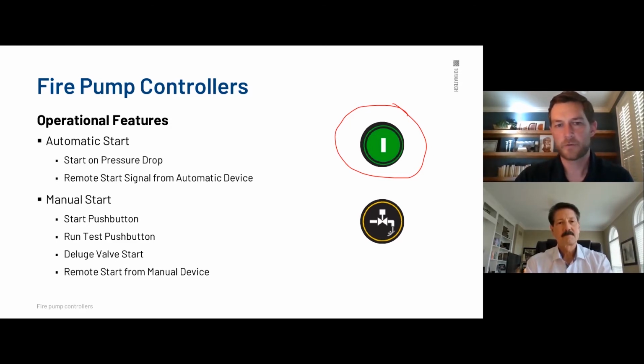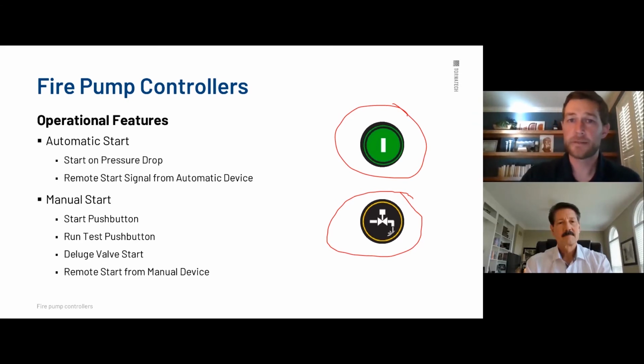This is our run test button, and Marty has already described that one as well. You press that button, it activates the solenoid, drains a tiny little bit of water, and will run your NFPA 25 weekly or monthly test. You also have a deluge valve start, or a remote start from a manual device, so a manual push button from somewhere. But typically, it's automatic starts on pressure drops, and then just your standard start push button there.